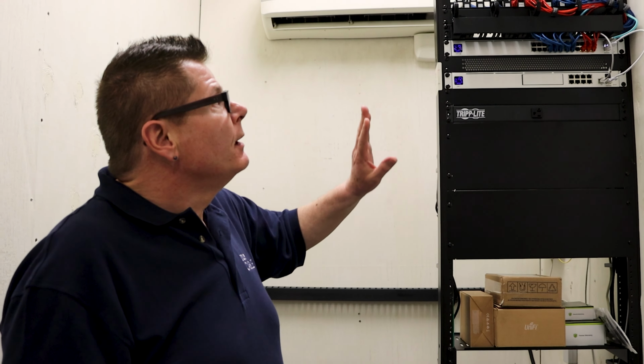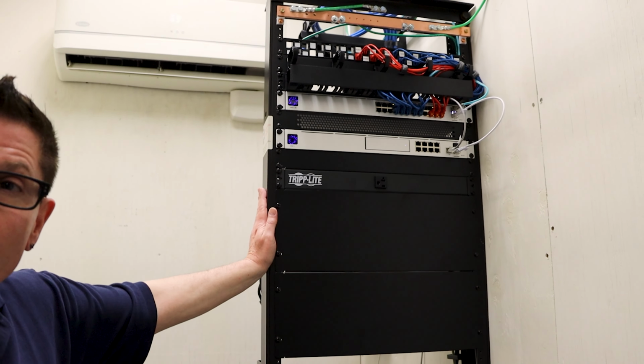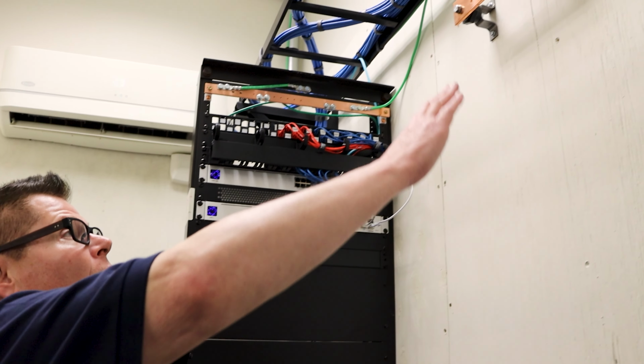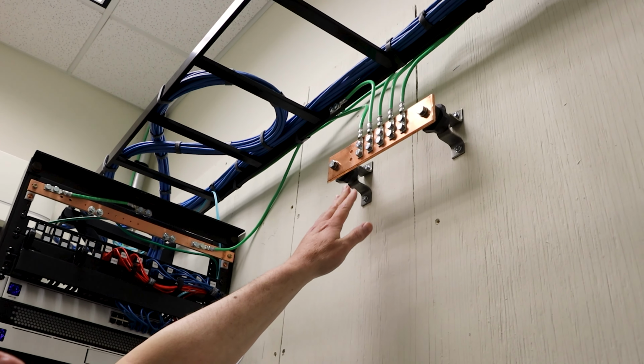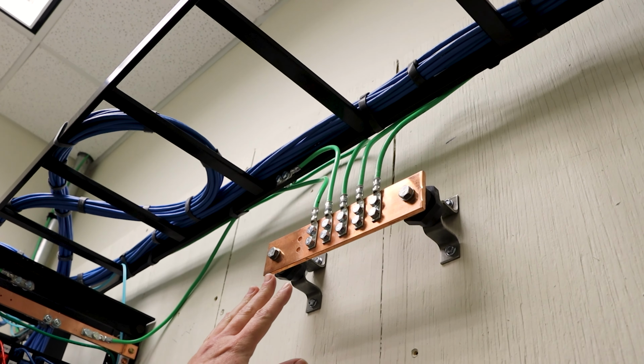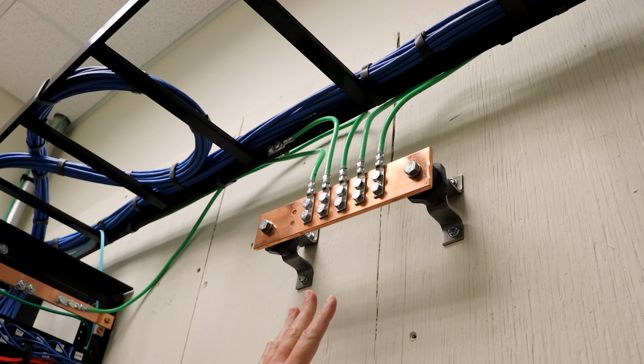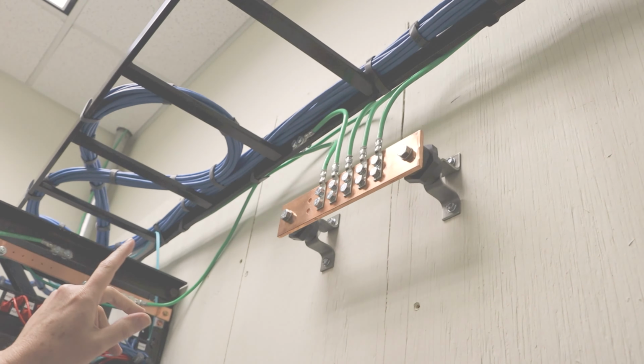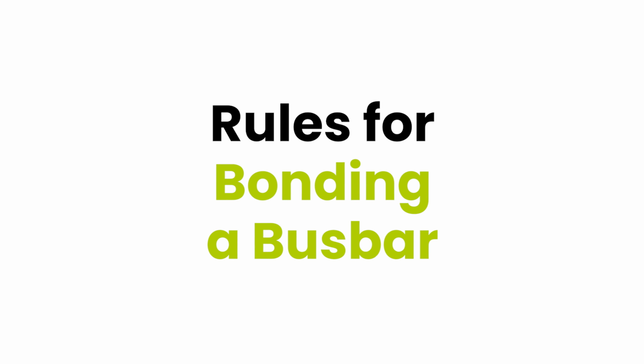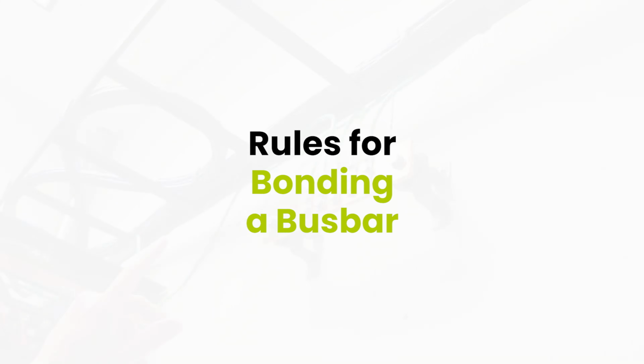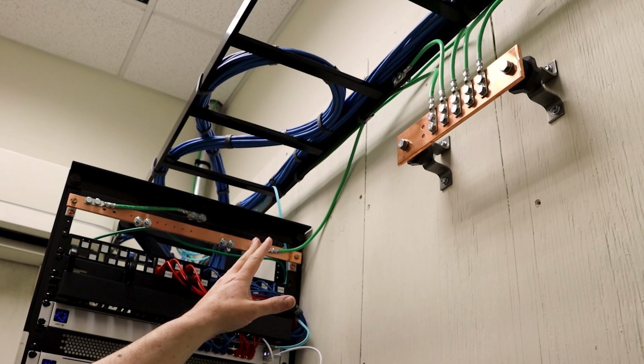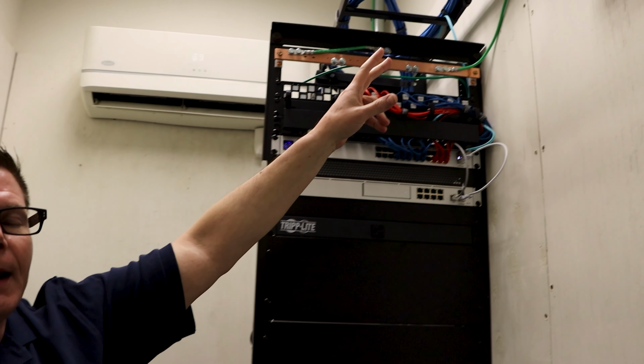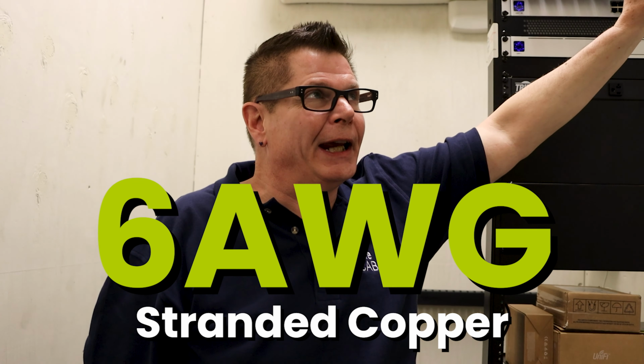Now, that applies to the communications technology sector because all metal, for example, in a telecommunications closet needs to be bonded to a busbar. And there are rules about how you bond it, and so we're going to talk about that right now.